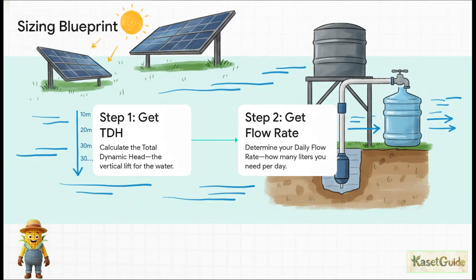First, your total dynamic head, or TDH—think of that as the total vertical distance the pump has to lift the water, from its source all the way up to your tank. And second, your daily flow rate, which is simply how much water you actually need each day. Once you have those two numbers, you can pick the perfect pump for the job.